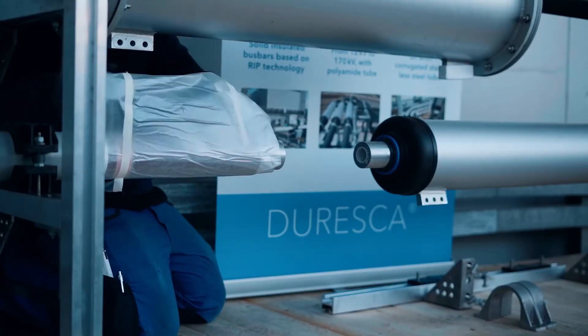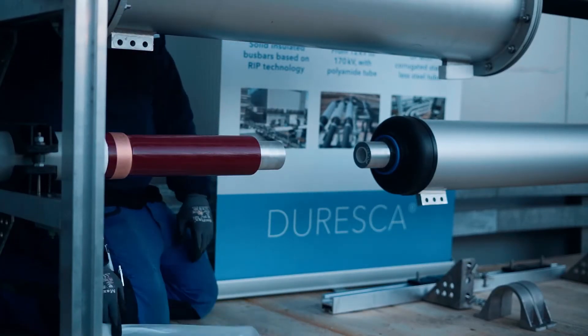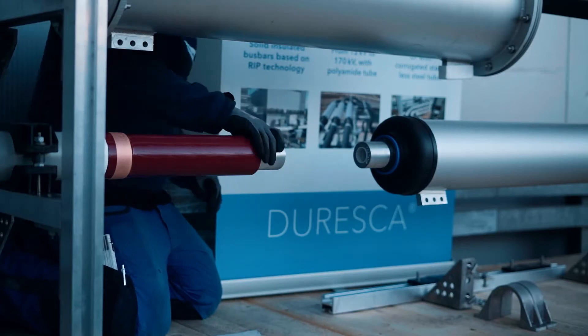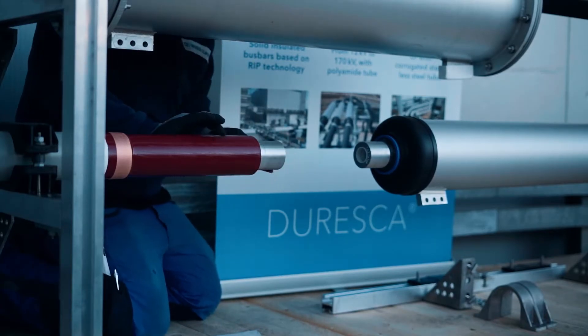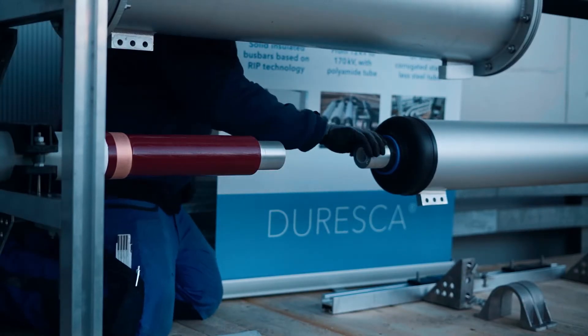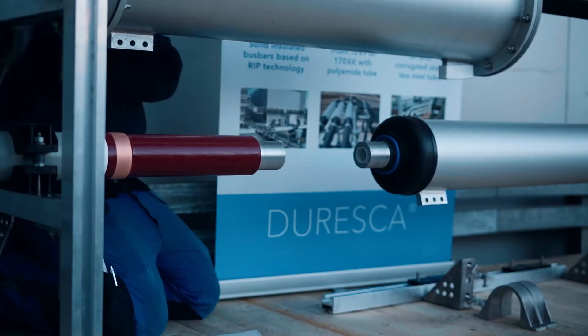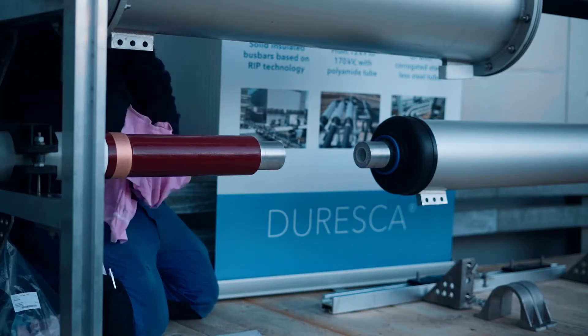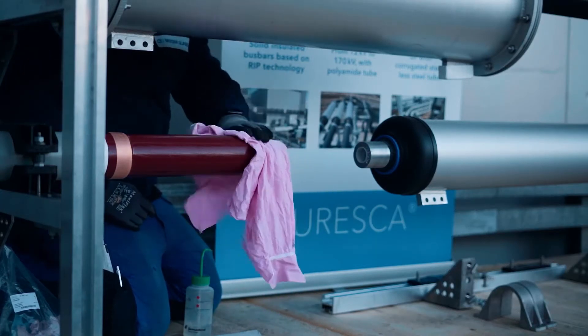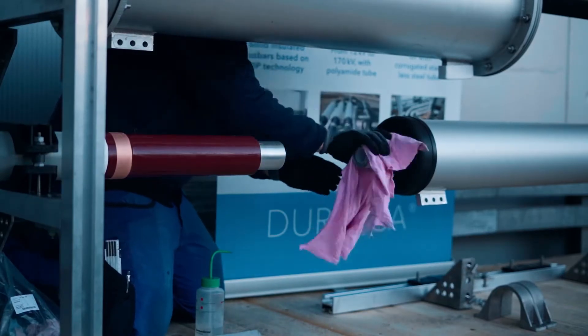Remove the plastic packaging and clean the contact surface carefully with a 3M Scotch-Brite pad. Remove metal dust with ethanol and a clean cloth. Grease the clean contact surface immediately with a thin layer of contact grease P1.